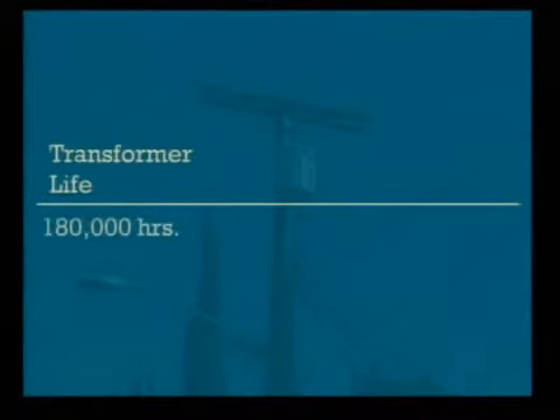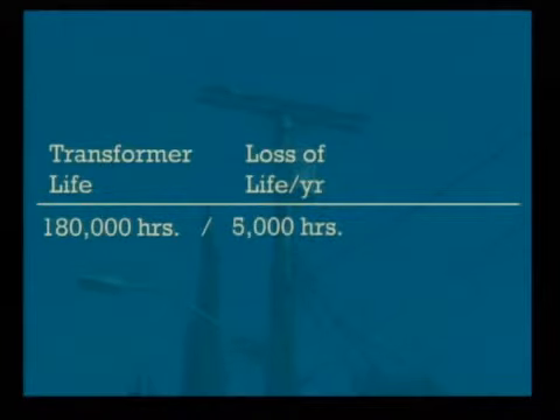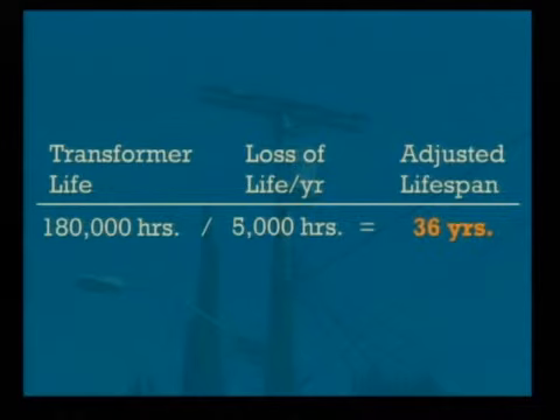So say your transformer's got a typical life of 180,000 hours, pretty industry standard. Based on all the load data collected, you calculate it's losing about 5,000 hours per year. That means for the first time ever, as a utility, we could predict how long these transformers would live. To my knowledge, no utility is able to do this for distribution transformers.